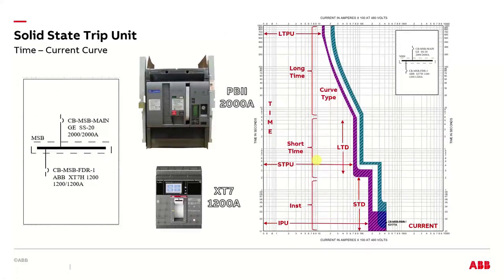Here's a typical curve, and this would be a solid state with LSI adjustment. You see it's all pretty complicated. Once again, your current is on your x-axis, your time on your y-axis, but you now have these three regions. You have long time, which in this case we're saying above 10 seconds. Short time, which is between a few cycles, like 6 to 12 cycles, and into the seconds region. Then you have your instantaneous region. So you have all these adjustments available to move these curves left and right and up and down. For example, your long time pickup is set in multiples of whatever rating the breaker is. If it's a 100 amp breaker and you want 80 amps to pick up, you'd set that to 0.8, so 80%. And then your short time, you can bring that up past the breaker rating.